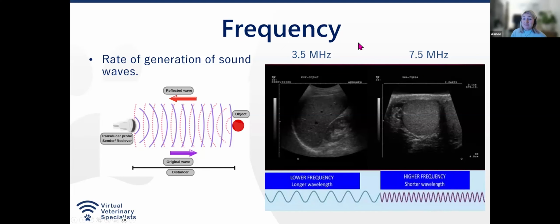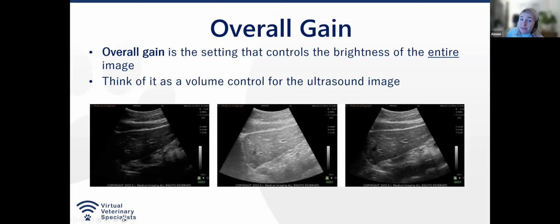Okay, so the next one is our overall gain. So think of this as the volume for your ultrasound machine. Okay, so it's how bright or how dark the whole image is going to be. And all the overall gain is doing is amplifying the returning echoes to your transducer throughout the depth of the image. Okay, so if you decrease the overall gain, you'll get an overall dark image like this one here. You increase it, you get a bright image like this one, or an oversaturated image. This is where your gain is set somewhere between the two. It's set perfectly, okay? Overall gain will be shown by a number on one side of your machine.